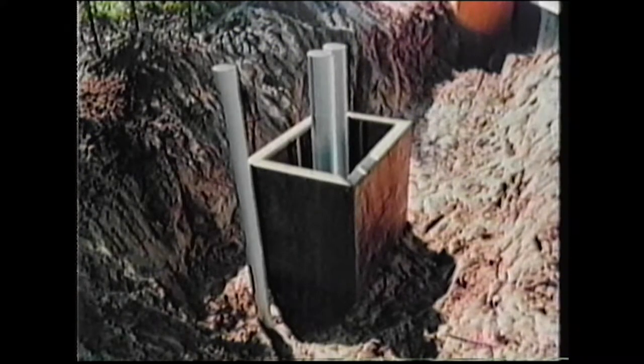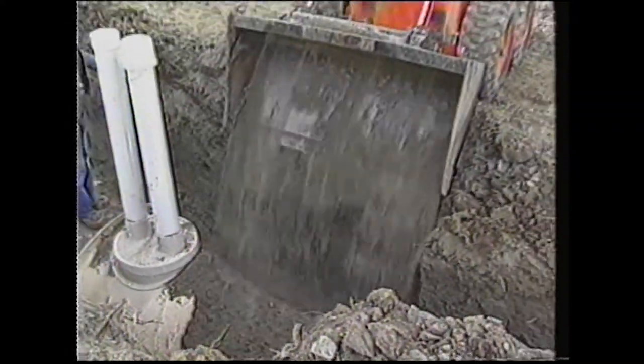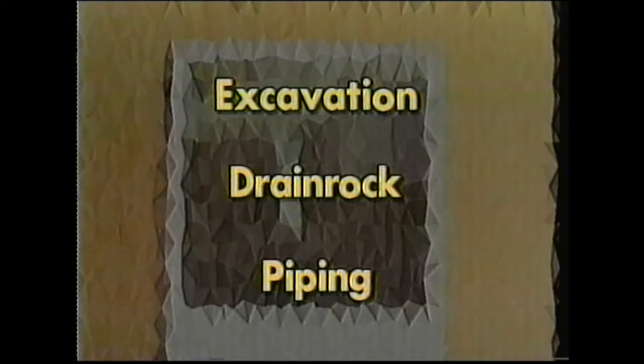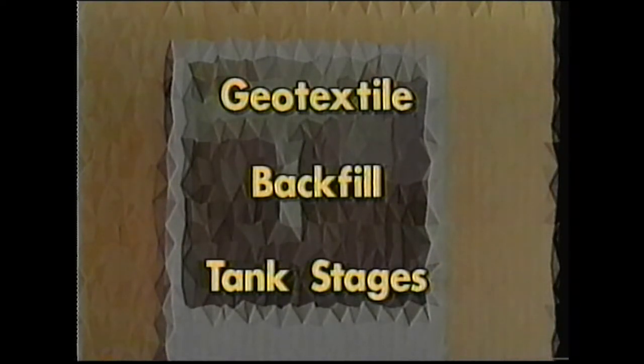Before backfilling, it's recommended to build an access hatch above your septic tank in case you need to do repairs on the tank later on. Pad and backfill the tank section with sand. When backfilling, you may lightly compact the soil — too much compaction may damage the pipes and tank. Remember to take photos during all major stages of construction. These are required by the Environmental Health Office as part of the permitting process. Photos provide an excellent record of your system installation and can also be handy when selling your house. Photos need to be taken during excavation, drain rock in place, all piping in place including perforated pipe, headers, and monitoring pipes, geotextile in place, and final backfill. Photos are also needed of the tank installation in place during backfill and at final stage.